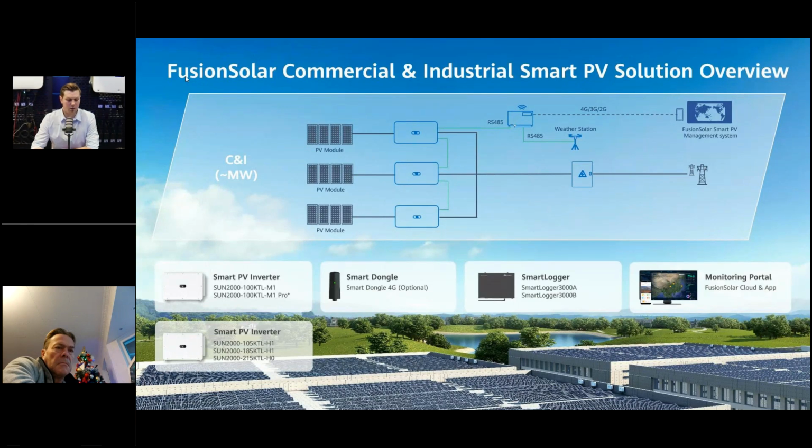Most commonly right now, the market is looking for the 215 kilowatts because of the high input current those inverters can withstand. Right now, the PV modules become more and more powerful. The short-circuit currents and the operating currents are also bigger and bigger, and manufacturers of inverters are trying to chase the manufacturers of PV modules according to this situation.